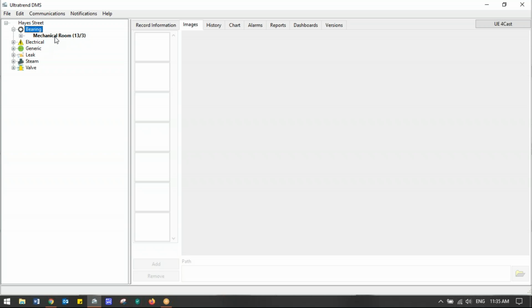You could have many routes built under here. Each route holds 400 test points or less. Suggested when you build these routes, 50 to 150 test points. Don't use the whole 400. That's much too big of a route. But in bold is the route name. I'll highlight that so you can see it.